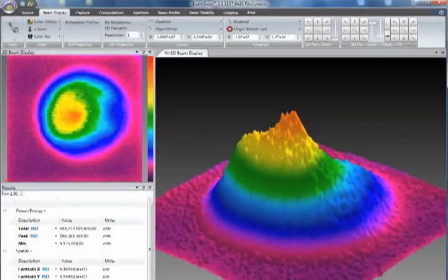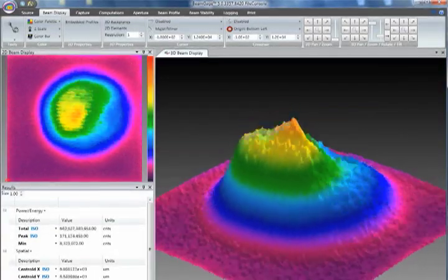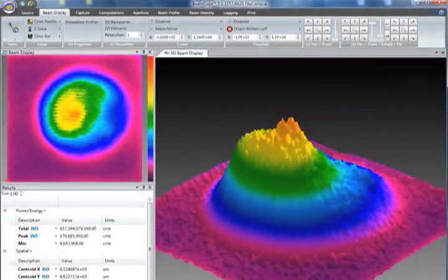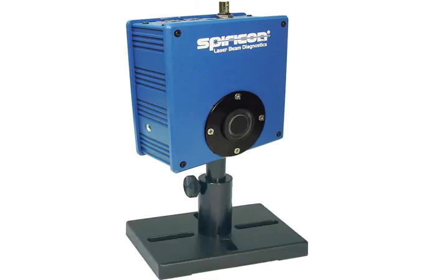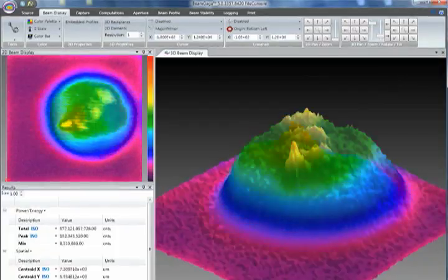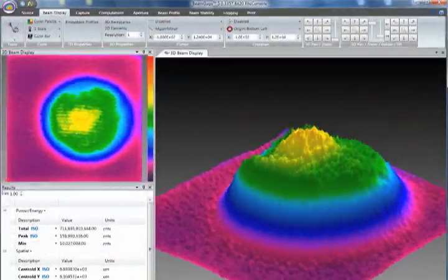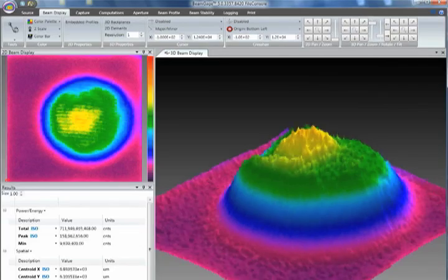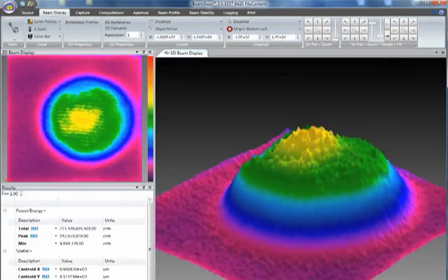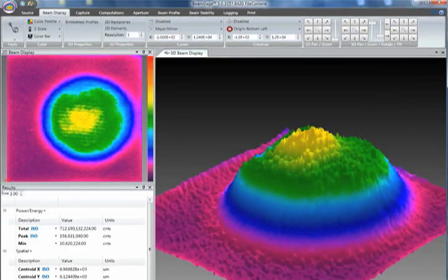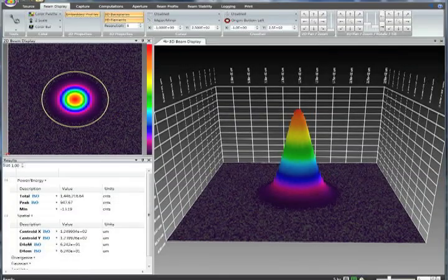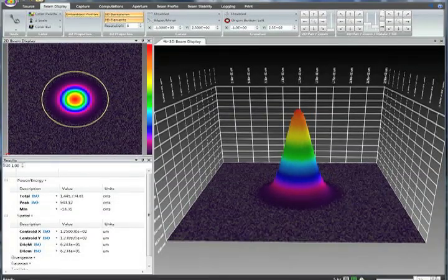This industrial 2-kilowatt CO2 laser beam produced poor welding joints. The Spiricon Pyrocam 3 beam profiler showed a highly asymmetrical beam. Adjusting cavity mirrors restored the beam in less than 10 minutes, eliminating downtime, scrap, and reducing cost per part.